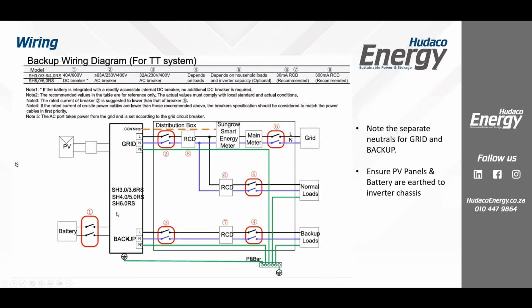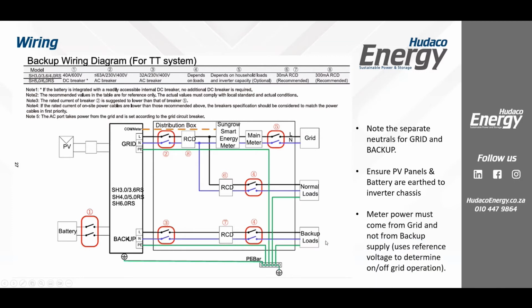There are 2 earthing points on the chassis of the inverter supplied for you already. And then here, the meter power: when you provide the power to the single phase meter that's supplied, power it please from the grid side, not from the backup port. Because what it does is it uses the voltage reference to determine whether we're in a load shedding scenario or not. And if you power it from the backup side, it doesn't quite know, well, it's detecting voltage here as opposed to detecting loss of voltage from here. So please, when you power the meter up, just take that from the grid side.